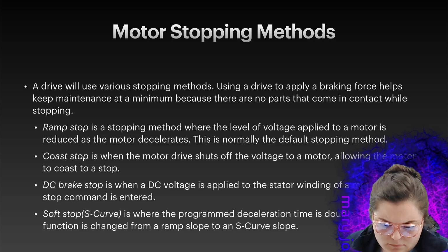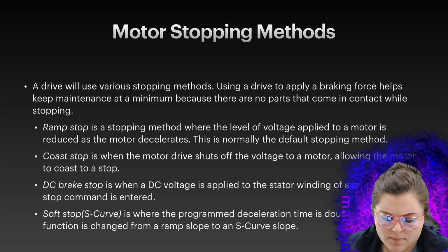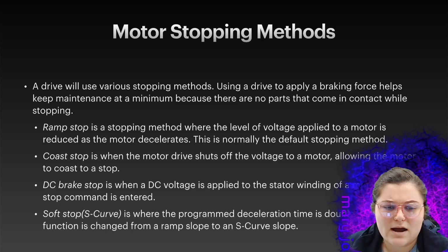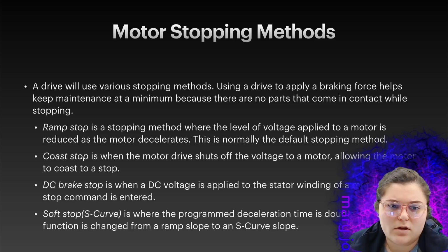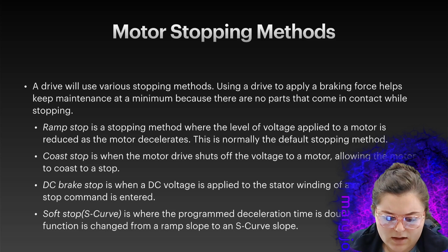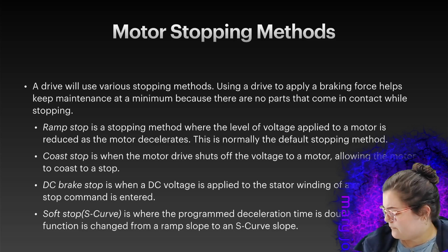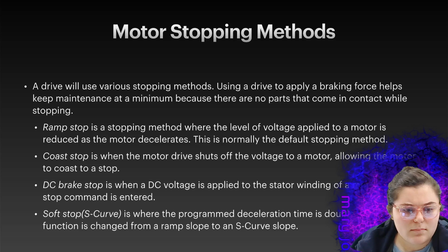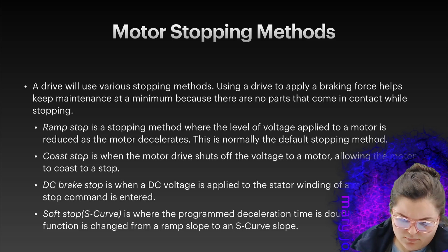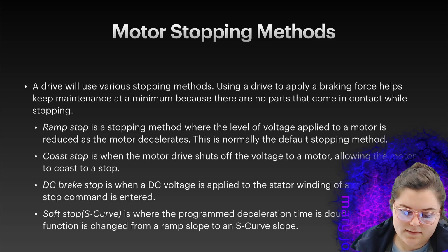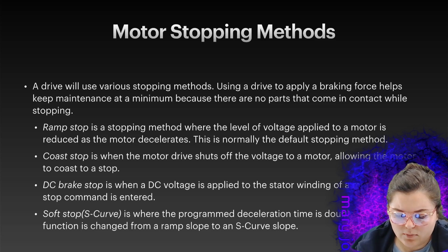Coast stop is when the motor drive shuts off the voltage to a motor, allowing the motor to coast to a stop. In most environments, that's a pretty good one because once you turn power off to the motor, it just literally stops whenever all the power is reduced. DC brake stop is when a DC voltage is applied to the stator winding of a motor after a stop command is entered. And soft stop, also called S-curve, is where the programmed deceleration time is doubled and the stop function is changed from a ramp slope to an S-curve slope.